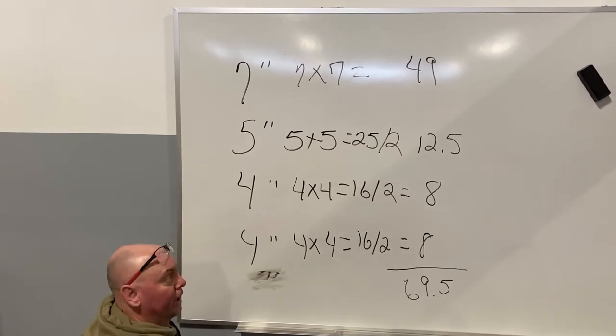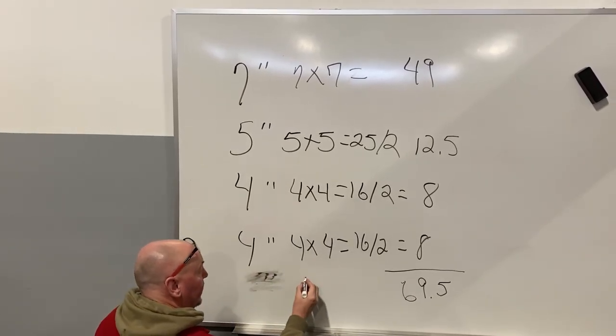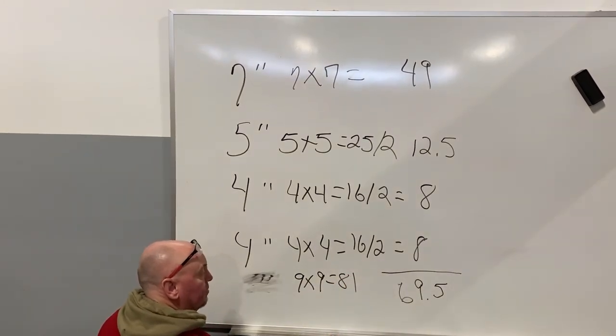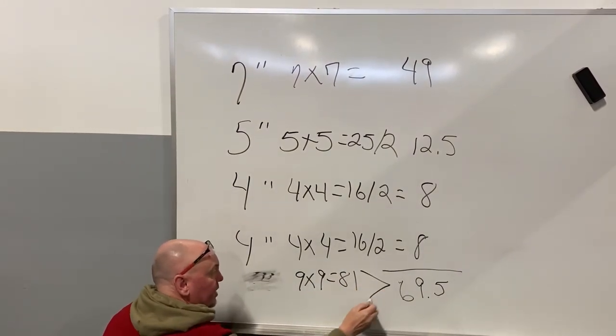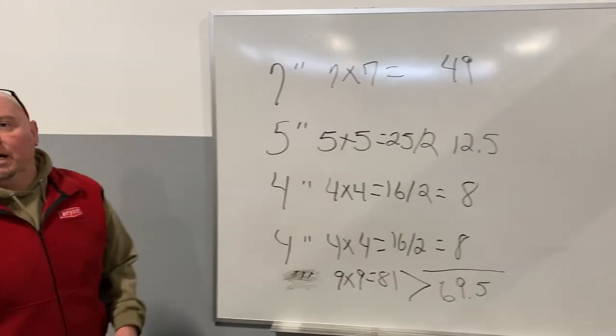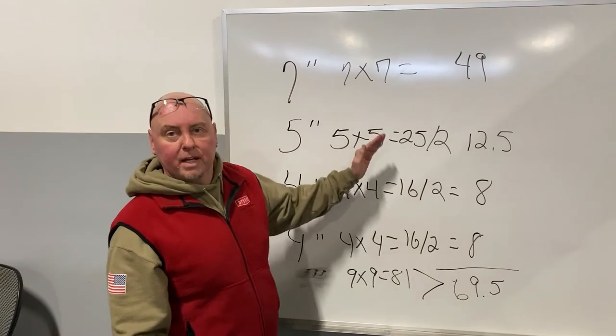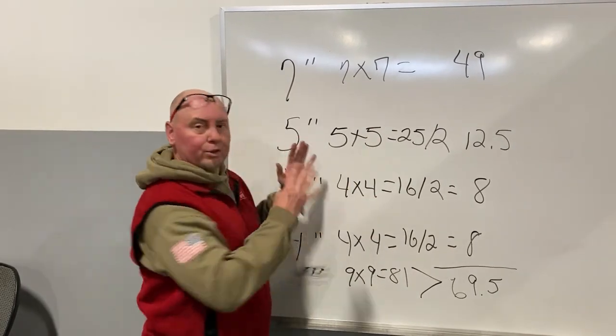Let's try another one. Let's do 9, 9 times 9, 81. 81 is greater than 69.5. So that would be the appropriate size pipe for that manifold, 9 inch would handle those appliances.